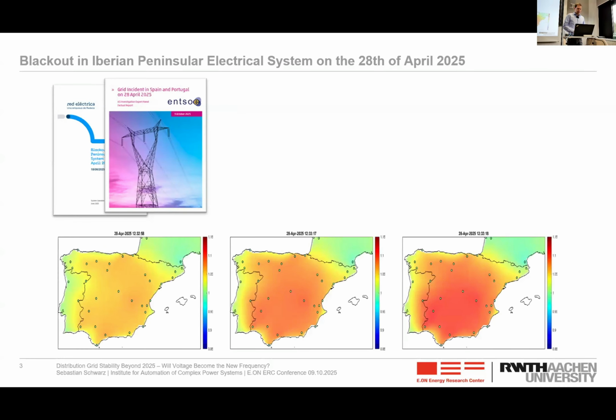It can already be concluded that this blackout was due to voltage issues, in this case overvoltage. So to shortly recapitulate what happened in Spain: on the 28th of April, there were oscillations in the system. Oscillations can either be forced or natural, and they also happened on this day. However, operators are usually quite aware of these oscillations and they know what to do. Also on that day, as a measure against this stability issue, they reduced the impedance of the system and reduced active power, because they were in a generating state, to the neighboring countries, basically France.